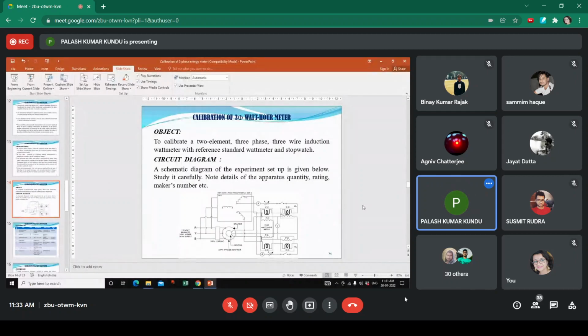The test condition mentioned specifies two power factor conditions, that is unity power factor and 0.5 lagging load power factor, which should be maintained. That can be easily set with the help of the phase shifter. So this is the circuit diagram, and the rated load current can be varied by two rheostats. One rheostat R1 is used in one phase, and another rheostat is used in another phase. Both rheostats should be adjusted simultaneously in such a manner that the current indicated by the two ammeters is the same. So 100% rated current means 5 ampere. According to the percentage loading, there are different percentage settings, so according to the ammeter reading, we can adjust the rated percentage current loading to the current coil.